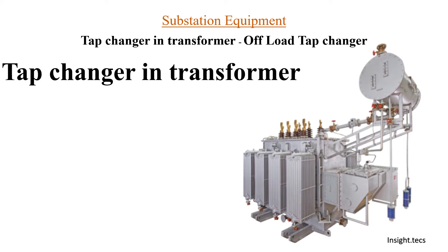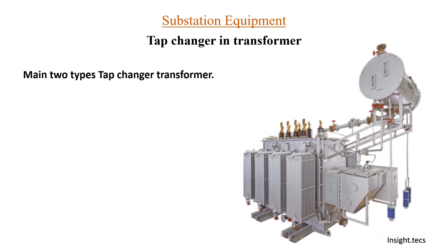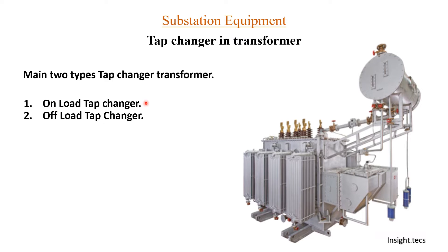In today's video, we are going to see about offload tap changers. Mainly there are two types of tap changers in a transformer. The first one is the onload tap changer and the second one is the offload tap changer. As the name suggests, in the onload tap changer, we have to change the tap positions when the transformer is in on condition — when the transformer is live, we can change the taps. In offload tap changers, when the transformer is in off condition, we have to turn off the transformer first, and only after that we can change the tap settings.